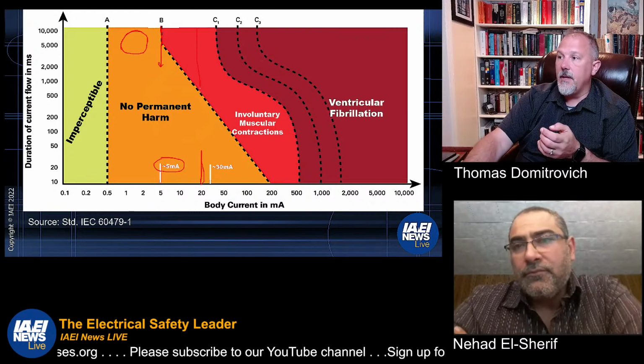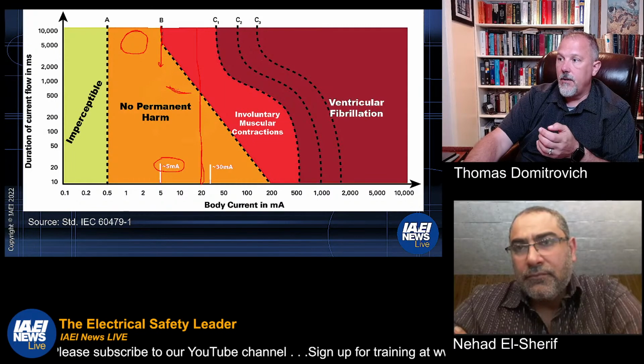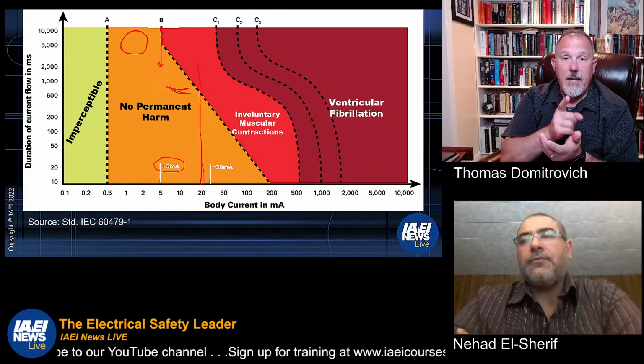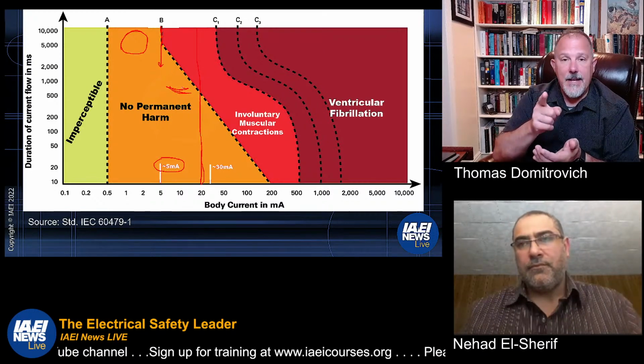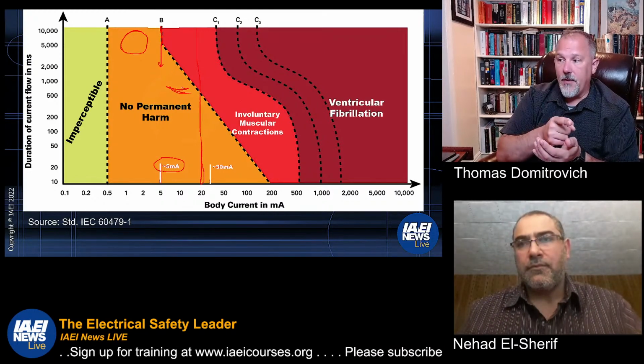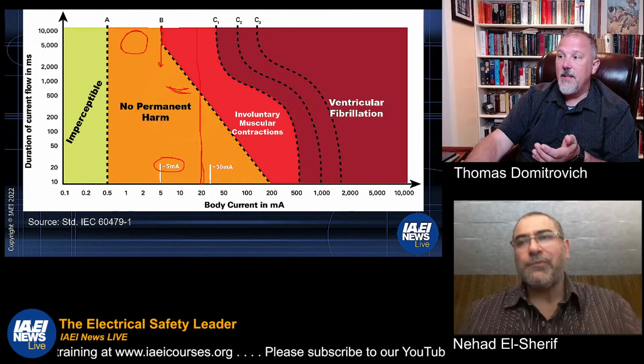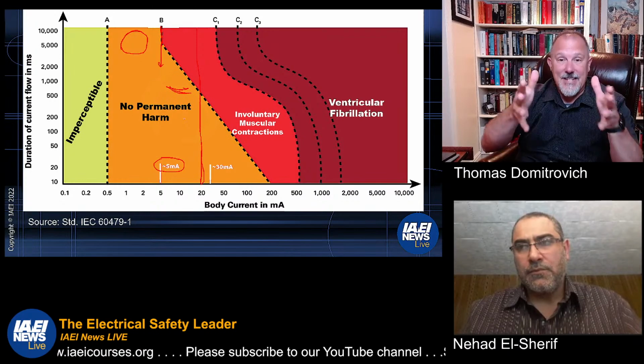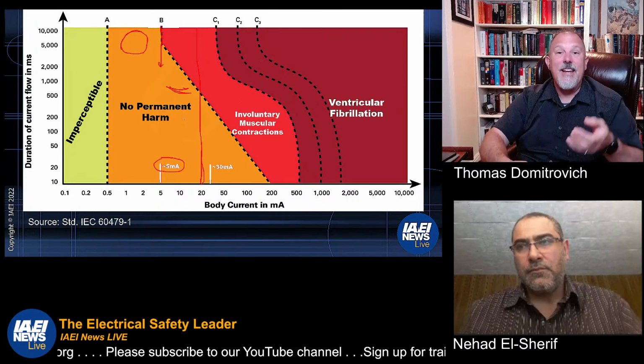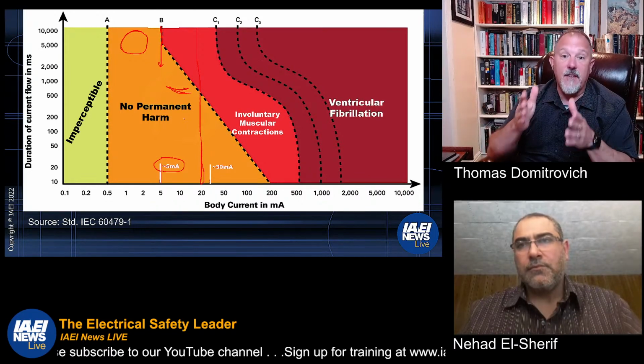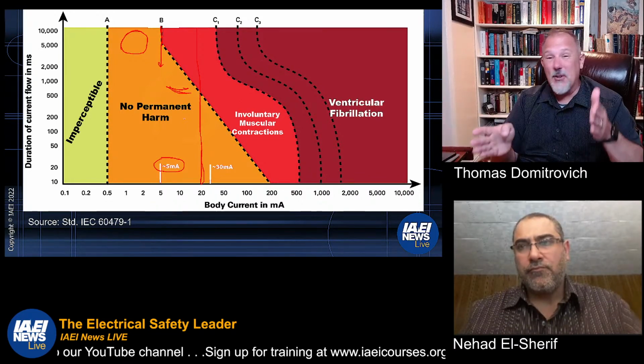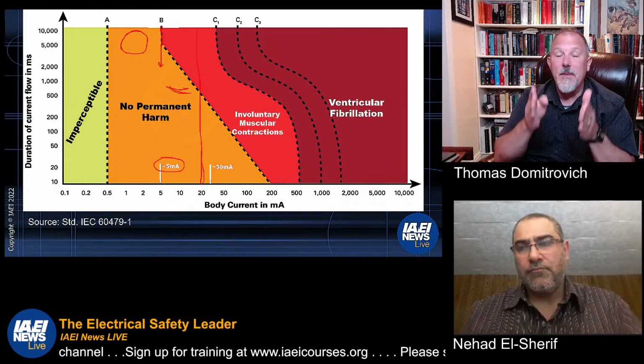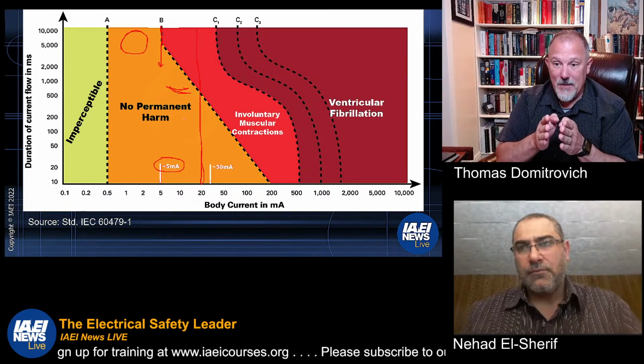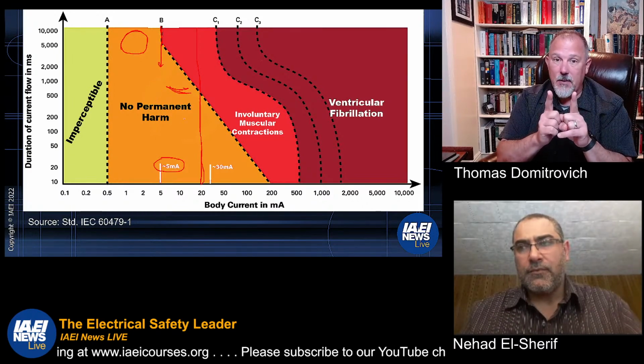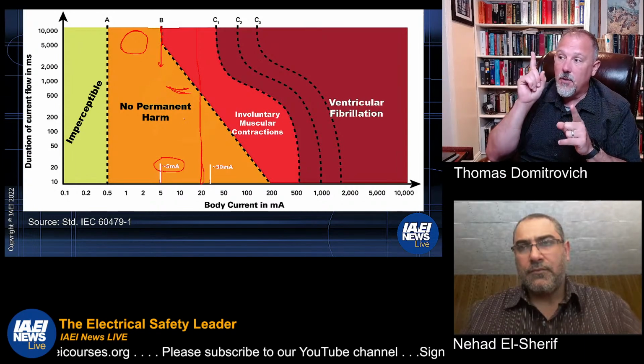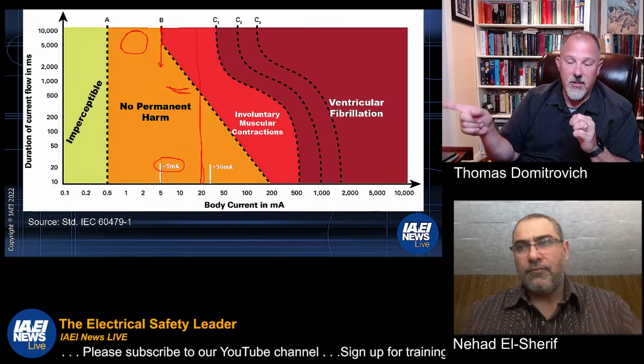Okay, so the vulnerability really is right in here where you could have a current, and this would be if the current is less than 20 milliamps, but greater than approximately 5 milliamps. If the circuit is such that that's how much current is flowing based upon you touching it, and the impedance of the conductor and all that other good stuff limits that current to less than 20 milliamps, but greater than 5 milliamps, a difference of about 15 milliamps, right? That 15 milliamp window is what you're looking at with regard to you could possibly have involuntary muscle contraction. Your heart's not going to go into defib.